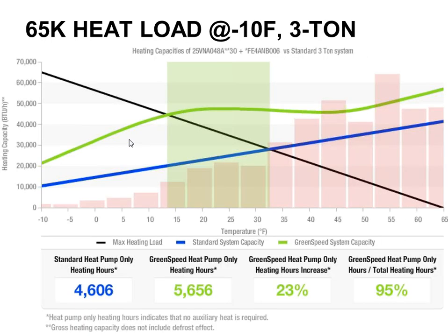There is actually an iPhone app as well as a website that Bryant and Carrier have that you can use to graph out that scenario for your specific customer situation. So I graphed one here randomly, a 4 ton heat pump on a 3 ton cooling load. So I graphed a 3 ton heat pump versus a 4 ton heat pump, a 3 ton regular heat pump versus a 4 ton Greenspeed heat pump. And you can see that the blue line was the regular one, the green line was the Greenspeed heat pump. All the operating hours in that green shaded box are hours that I now get to run my heat pump that I could not have done with a regular system.